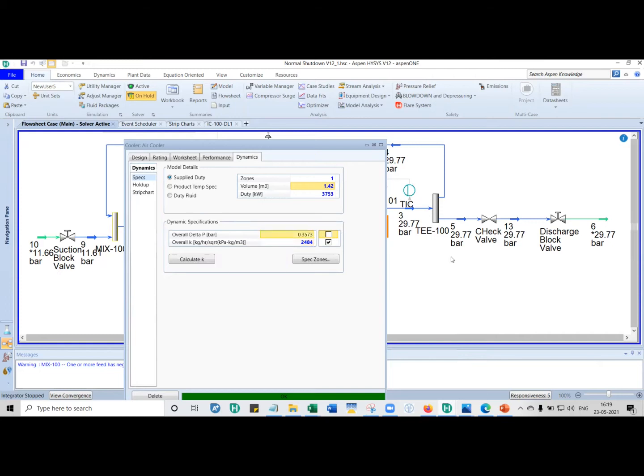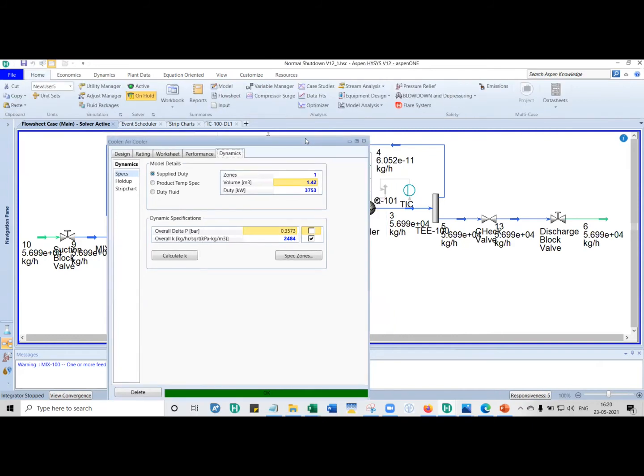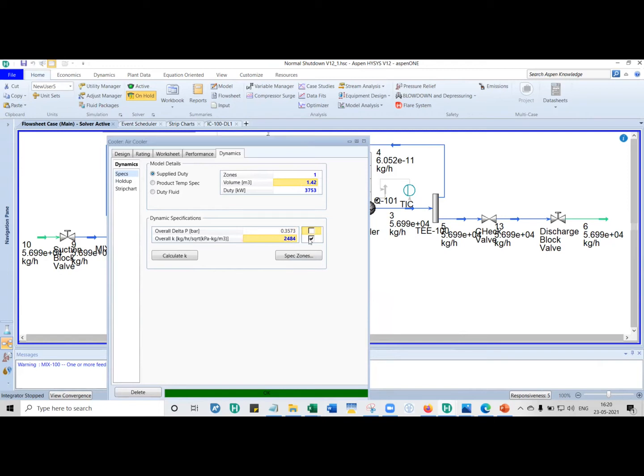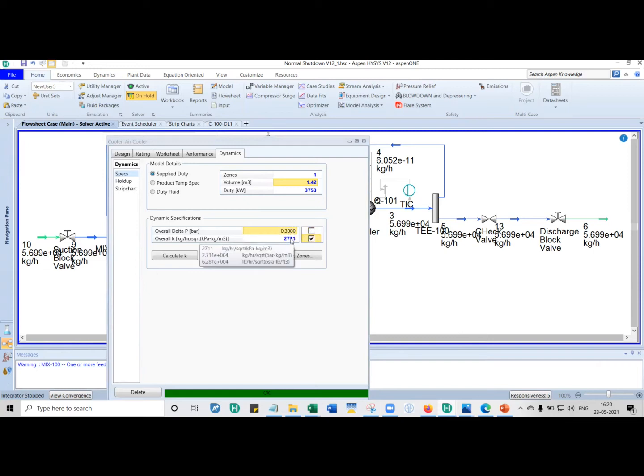So the purpose of putting this K-value loss coefficient is: depending on the flow rate, if the flow rate is changing — say it's currently 57,000 kg/hr and it goes to 60,000 kg/hr — using this K-value HYSYS will calculate the new pressure drop. So if it was 0.35, it can become 0.36 or 0.37. You compute the K-value from your heat and material balance — put in, say, 0.30, and it will automatically calculate the K-value. Then you switch the boundary condition, so if the flow rate increases, 0.3 can become 0.32, and if the flow rate decreases, the pressure drop also comes down to 0.29 or 0.28.